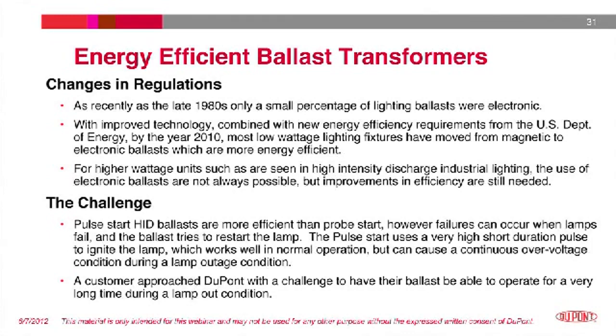Finally, for a transformer application, we will discuss ballast transformers used for high-intensity discharge lamps. As recently as the late 80s, only a small percentage of lighting ballasts were electronic. With improvements in technology, combined with new energy efficiency standards from the U.S. Department of Energy, by the year 2010, most low-wattage lighting fixtures have moved from magnetic ballast to electronic ballast, which are much more energy efficient. For higher wattage industrial lighting applications, the use of electronic ballast is still not fully feasible. However, these applications still required more energy efficient designs, so manufacturers moved from probe start to pulse start ballast designs. The beauty of the pulse start ignition of the lamps is a significant reduction in the total energy used to start and operate the lamps.